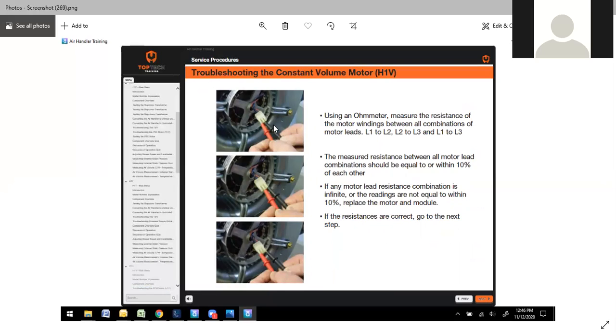At that point, using an ohm meter, you've got 3 wires here. L1 to L2, L2 to L3, and L1 to L3. So you're going to ohm out each combination. The measured resistance between all motor leads should be equal to or within 10% of each other. If any motor lead resistance combination is infinite or the readings are not equal, you'll usually see one way off. Replace the motor and the module. If the resistances are correct, go to the next step.